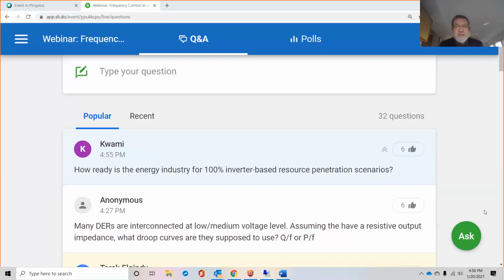Okay, here's a couple of DER questions. I know DER wasn't the focus of this, but maybe you could entertain them. Many DERs are interconnected at low or medium voltage level, assuming they have a resistive output impedance—what droop curves are they supposed to use, QF or PF? And a related question: for coordinated inverters on the distribution system, is it better to socialize their frequency responses or manage as a single IBR?